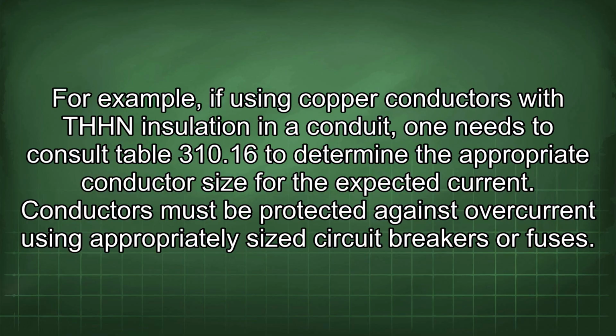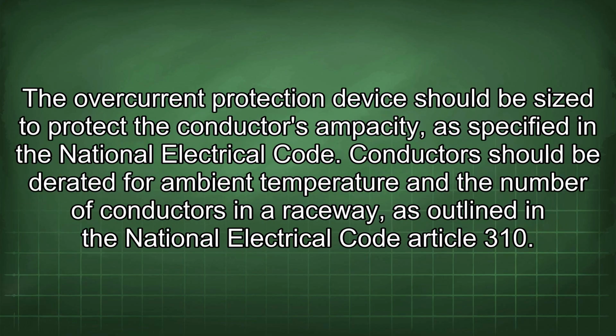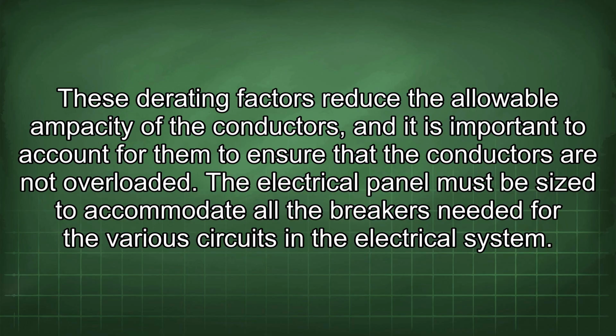Conductors must be protected against overcurrent using appropriately sized circuit breakers or fuses. The overcurrent protection device should be sized to protect the conductor's ampacity, as specified in the National Electrical Code. Conductors should be derated for ambient temperature and the number of conductors in a raceway, as outlined in the National Electrical Code Article 310. These derating factors reduce the allowable ampacity of the conductors, and it is important to account for them to ensure that the conductors are not overloaded.